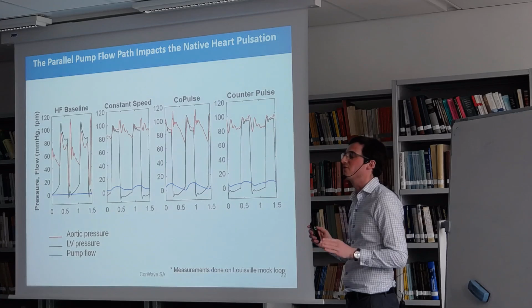And then I touched on the blood compatibility of the pump. We have continuous testing going on at CorWave, where on a weekly basis we test our pumps in different configurations to see the impact on hemolysis. Hemolysis is blood destruction. So obviously we're introducing a foreign device to the body. There's a movement involved in it. It's foreign materials and everything. There will be a certain amount of blood destruction. However, one has to minimize it, and that's what we're evaluating on a continuous basis.